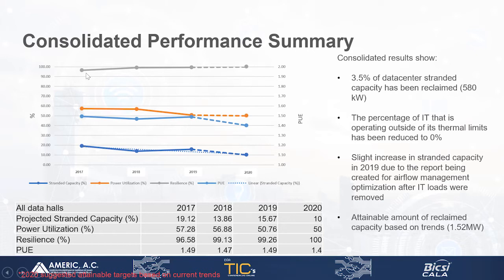At the same time, they increased the resilience of the IT hardware in the data centers. So close to 5% of the hardware in the data centers was exposed to bad environmental conditions, and they reduced that over 2 years to effectively zero. And this was also occurring when they were rapidly changing the IT configuration. The total power dropped slightly, but they installed a lot of high density equipment and took out a lot of legacy equipment in these rooms.